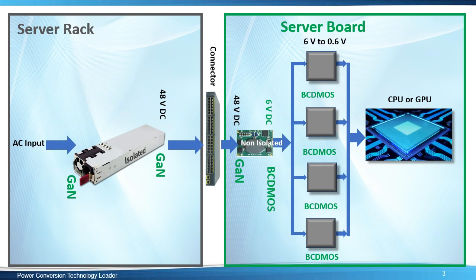Alternatively, for a given cross-section, a 48-volt distribution bus can deliver four times the power of a 12-volt system with the same bus loss. The most efficient way to convert power from 48 volts to point of load is a two-stage conversion with intermediate voltages of 12 volts or maybe 6 volts. Next, we'll look at what topologies can be used to support this architecture shift.